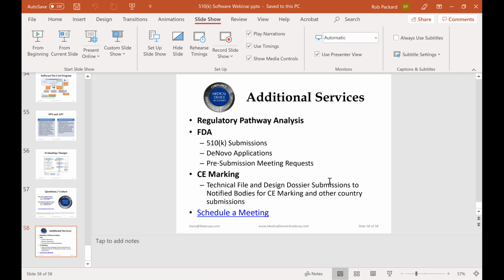And I've seen this at companies I actually was the quality manager at. We had a multi-parameter monitor company, CastMed, that I worked at. And that's how we did it. We had 100% of the bugs. We tracked them in a tool that was similar to Bugzilla and Jira. And we didn't conceal any of that from the FDA because they can get it all anyway when they come for an inspection. So the more important thing was how are you tracking it, and what is your method of determining whether this is something that's acceptable to release or not to release? Because they expect there to be bugs.